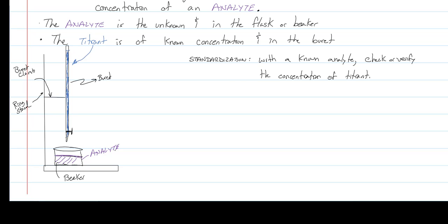Masses are easier and more accurate to measure than volumes. Why? Well, masses do not change with temperature. So you might have a perfect volume, your eye level is perfect, it's within 0.00001 milliliters of what it should be, and then it's 2 degrees warmer. Now it's off. So that's why we use the mass to do this, and you have to do it each time you use it, technically.